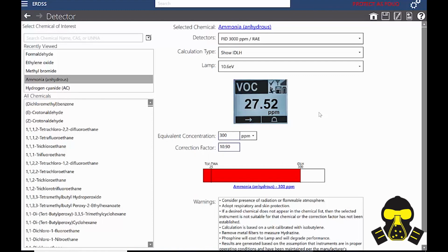They're really great at that mid range, but once you go over that, they start to fluctuate quite a bit. And you're also going to start poisoning your sensor quite a bit too, and getting coatings on it. So you've got to remember all that.